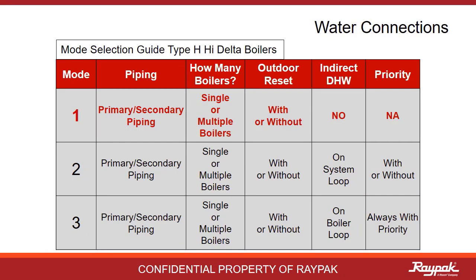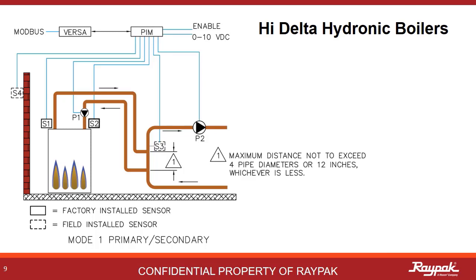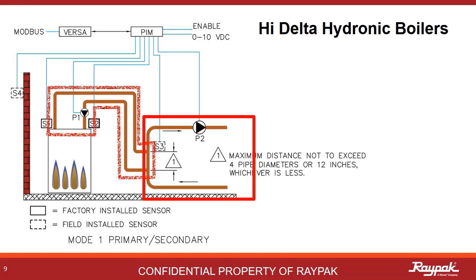First, we will present Mode 1 with primary-secondary plumbing. This is by far the most common configuration on a hydronic boiler. Here is a diagram for a Mode 1 primary-secondary system with a single boiler. It is primary-secondary because there are two loops: the boiler loop and the system loop. That is how you should refer to them — not the primary loop and the secondary loop, as what you mean by primary loop might differ from what the person you are speaking to thinks is the primary loop.